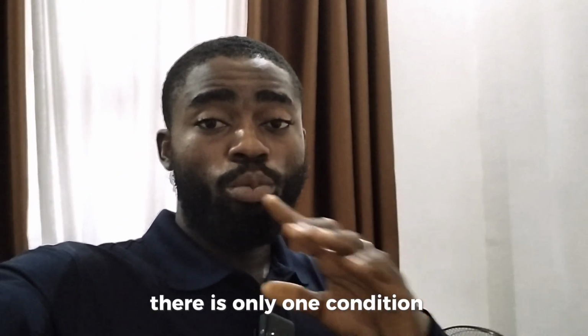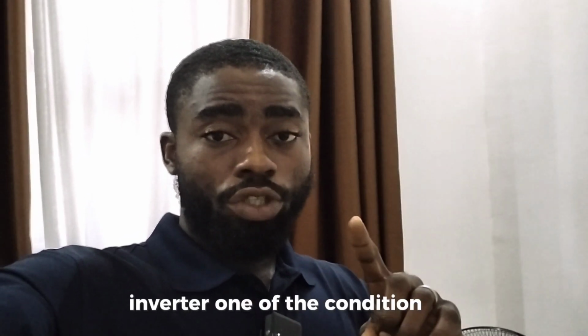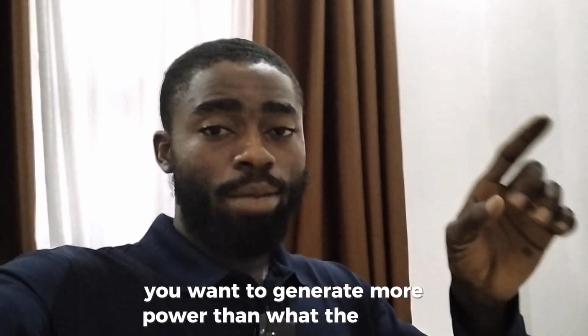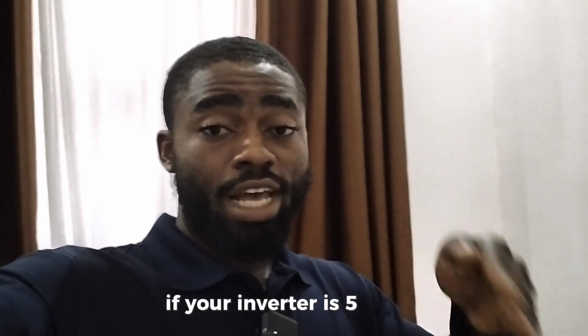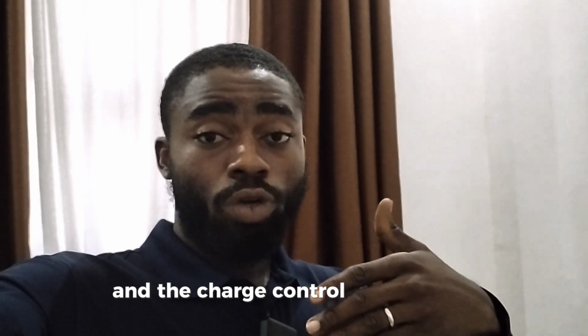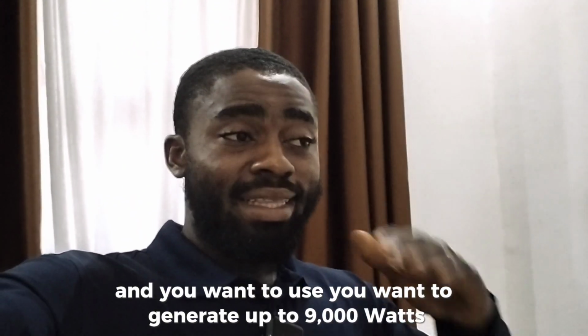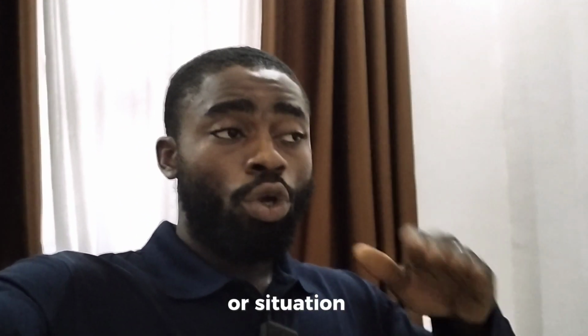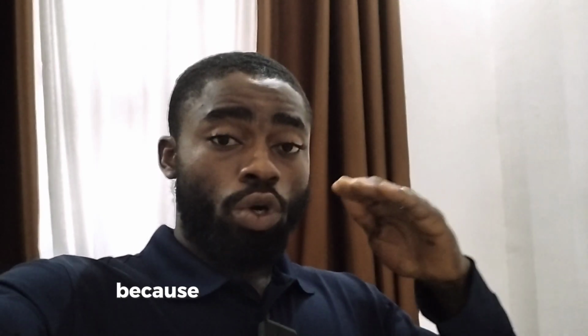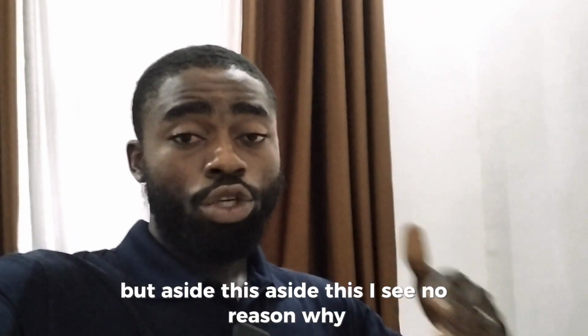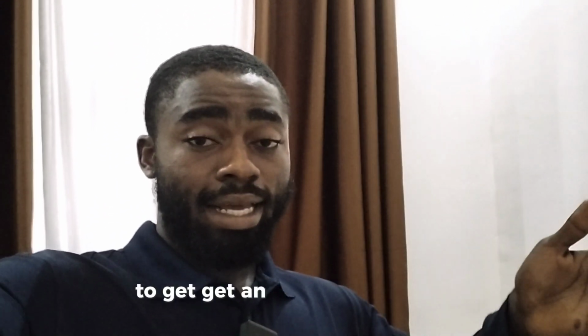There is only one condition that requires an external charge controller alongside your solar hybrid inverter: when you want to generate more power than the hybrid inverter can handle. For example, if your inverter is 5 kVA and the charge controller is rated 4,500 watts, but you want to generate up to 9,000 watts, that's the only situation where you need an external charge controller, since the extra 4,500 watts will be handled by it.